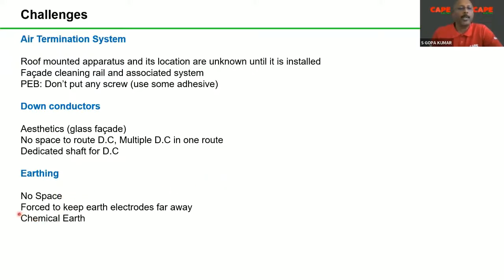This is the situation. We are always forced to keep earth electrodes far away from the building, which is also a violation, because if you keep it far away, as I said, due to surge impedance, the potential differences will be very high, or potential differences will be higher and higher.